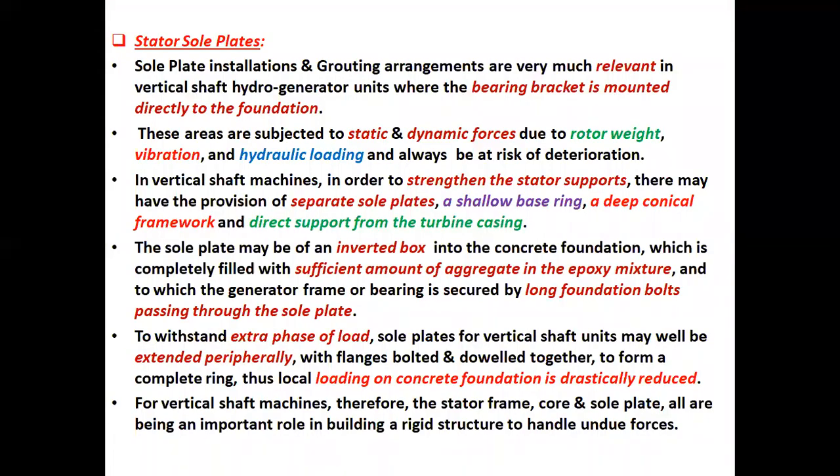The diagram presents the circular formation as well as a segment of a lamination. Stator sole plates: installation and grouting arrangements are very much relevant in vertical shaft hydrogenerator units where the bearing bracket is mounted directly to the foundation. These areas are subjected to static and dynamic forces due to rotor weight, vibration and hydraulic loading, and are always at risk of deterioration. In vertical shaft machines, in order to strengthen the stator supports, there may be a provision of separate sole plates, a shallow base ring, a deep conical framework, and direct support from the turbine casing.